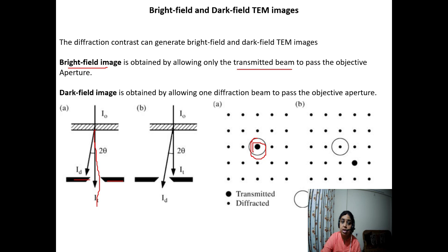And if we stop it, we allow just the diffracted beam to pass through. This kind of image is known as a dark field image. So the dark field image is obtained by not allowing the transmitted beam through the objective aperture. However, for the bright field image, we allow the transmitted beam to pass through the objective aperture. So this is the main imaging mode in the TEM machine, bright field and dark field. In bright field, the transmitted beam is allowed to pass through the objective aperture, and in the dark field image, only the diffracted beam is allowed to pass.